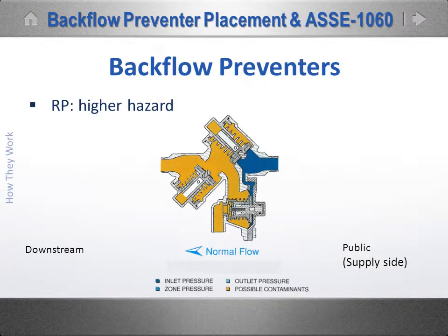Now let's consider a full failure of the number 2 check valve, one that might occur if the device is knocked out of round or just a mechanical failure. It's essentially the same event with the exception that due to the larger valve opening, there is actually a higher flood rate. Now you have water flowing through the relief valve at full head pressure. Again, if this is a large or multi-story building, that is a lot of water very fast.